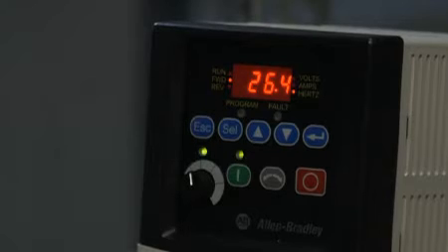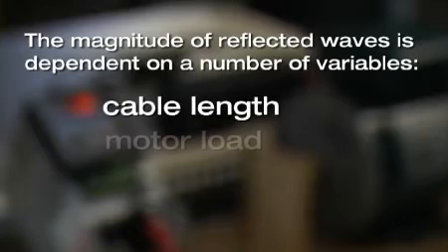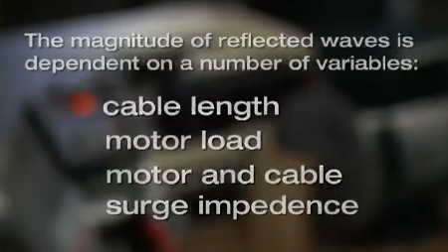VSDs generate pulses with fast rising edges that can create voltage reflection. The magnitude of these reflected waves is dependent on a number of variables: cable length, motor load, motor and cable surge impedance, etc.